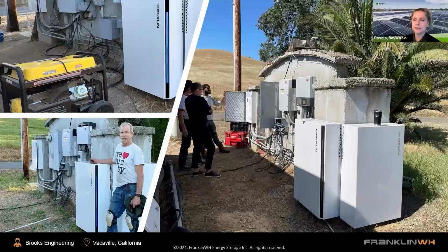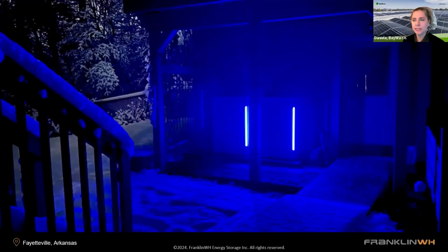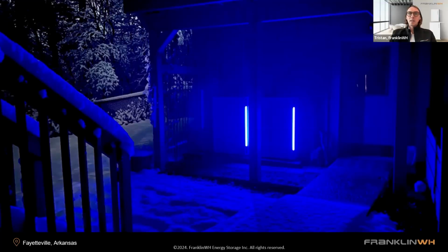Thank you. There's another technical question: can you explain the differences between the Gen 1 and Gen 2 PV input? For example, existing 11.4 kilowatt, 60 amp PV, looking for Franklin. I want to make sure I understand the question correctly—the PV input hasn't changed from the earlier versions of aGate to newer versions; it's always been listed at 80 amps. One key difference, though, is the ability to support the quad breaker. So if you have an inverter 7.6 or less, you may be able to quad it up without using a combiner panel. I hope that answers the question.